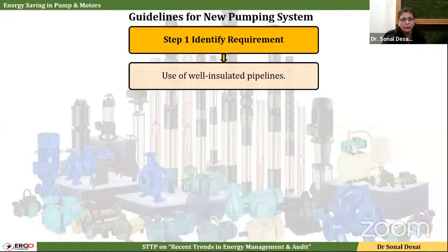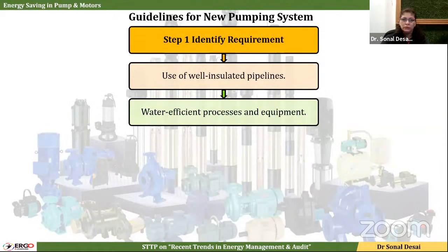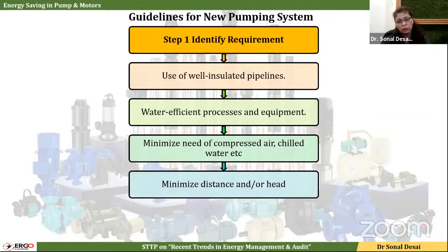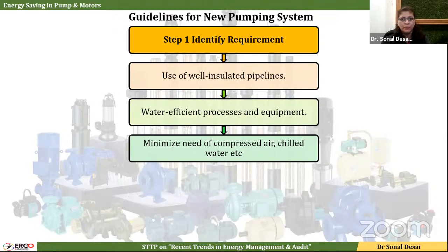So to summarize the pump part of energy saving, we have to identify the requirement based on the pumping requirement. The pipeline should be well insulated, because most of the time we handle either chilled water or hot water, or sometimes steam is passed on. So it should have proper insulation. It should also have water efficient process and equipment. Not only pumps, they are also playing a vital role in overall plant energy saving. Minimize the need of compressed air and chilled water. If you reduce the requirement of HVAC chilled water, ultimately the pumping load will also reduce. Minimize distance and height, because if the distance is lower, then pumping power will also reduce.